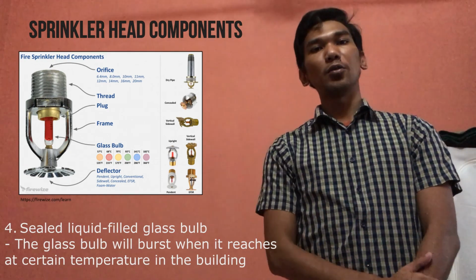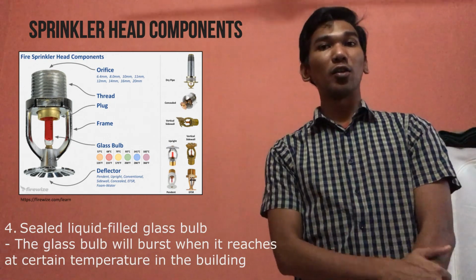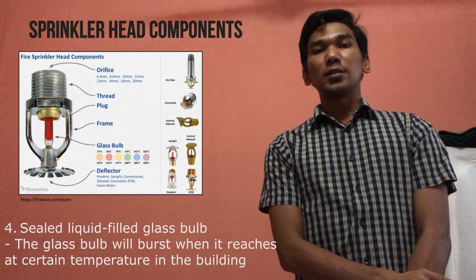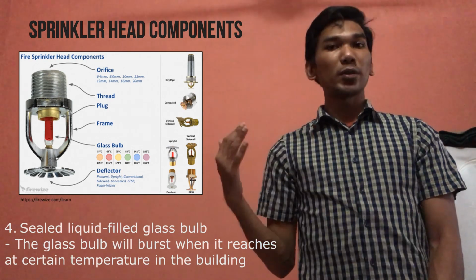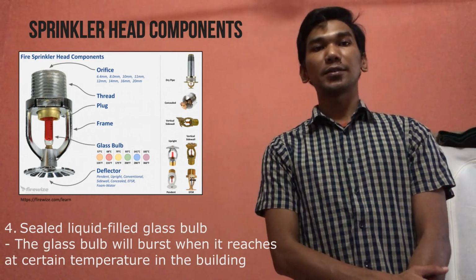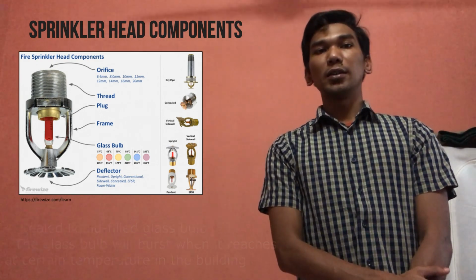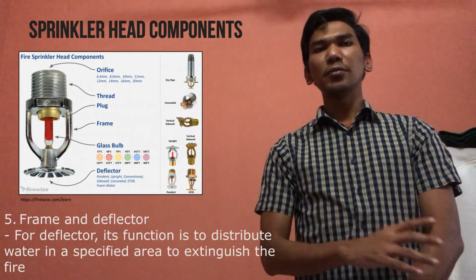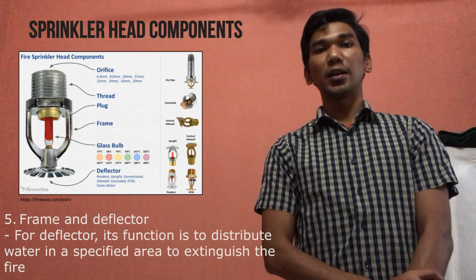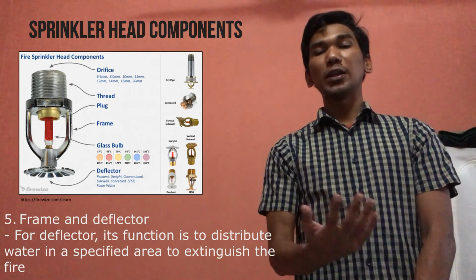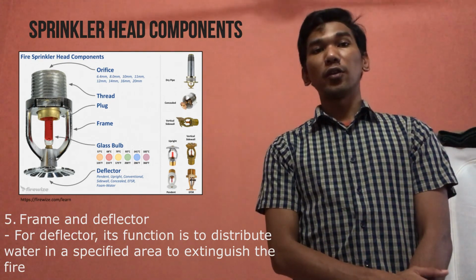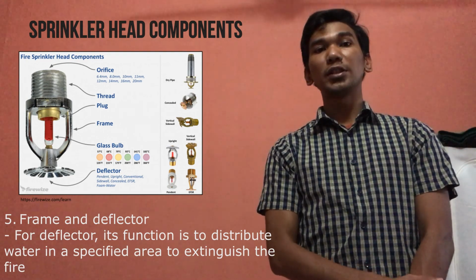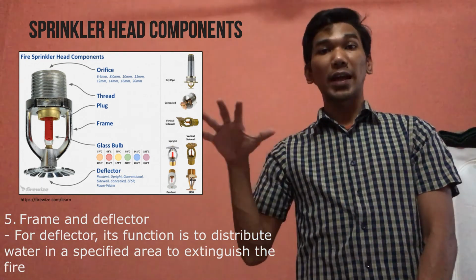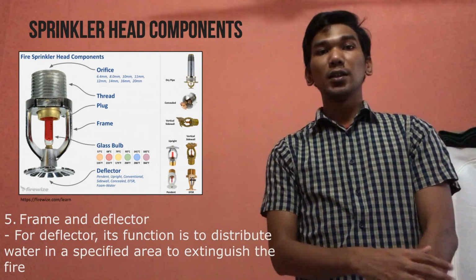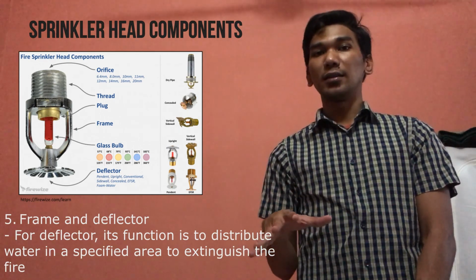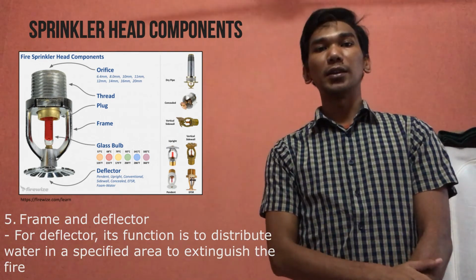The common color that we see or that is used is the red color, which has a maximum temperature of 68 degrees Celsius. After that, the frame and deflector. So for the frame, it has many finishes and it depends on the type of sprinkler that will be used. So for the deflector, its function is to distribute the water in a specified area to extinguish the fire. So the deflectors depend very much on the style.